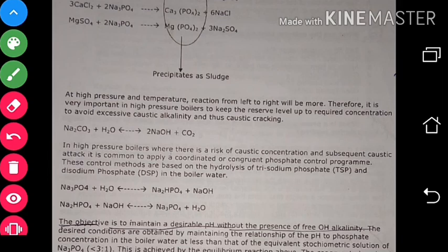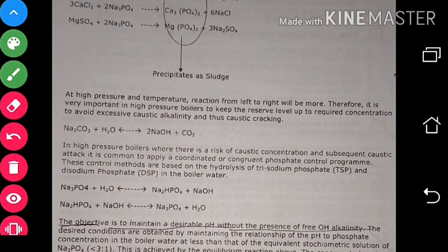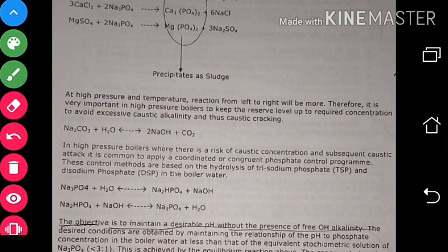Undesirable impurities in the boiler water form sludge, which can be prevented by boiler water treatment. Sludge deposits on the surface can lead to foaming and priming, which adds water into the steam, causing carry-over and water hammering. Fourth, to maintain the boiler water in an alkaline condition and free from dissolved gases. Fifth, to prevent entry into the boiler of foreign matters such as oil, waste, mill scale, ferric oxide, copper, and sand.